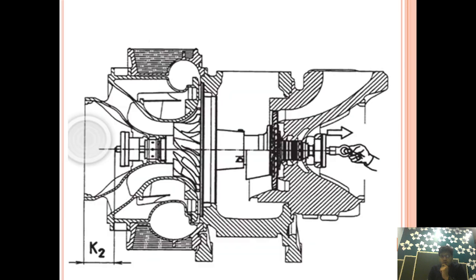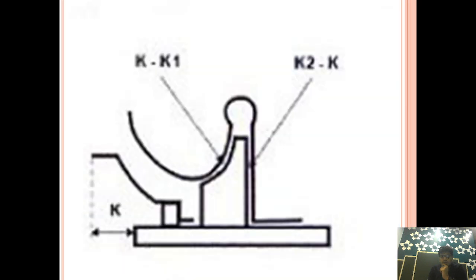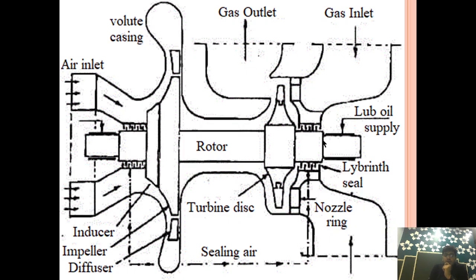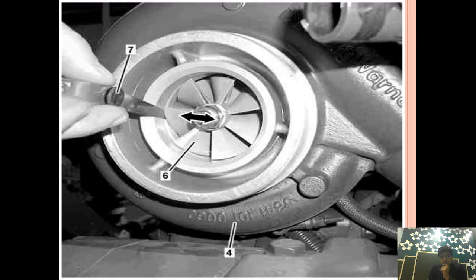There should be adequate clearance between these components; otherwise, if the clearance is not proper, it may get stuck. To ensure that, we put a feeler gauge — as you can see here, we are putting a feeler gauge and checking the radial clearance on each side of the turbine plate. This ensures that when the component gets heated up, it will have sufficient clearance and does not seize.